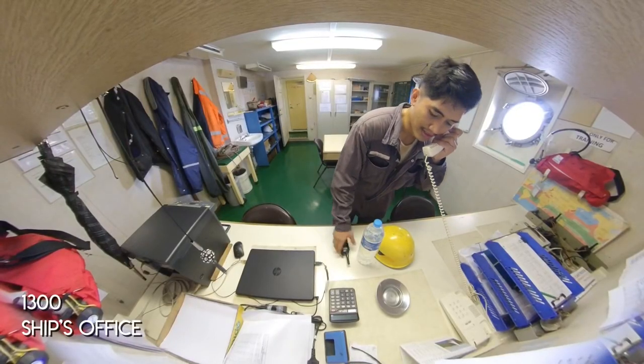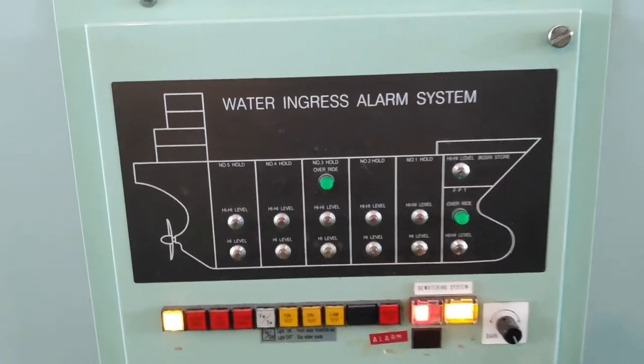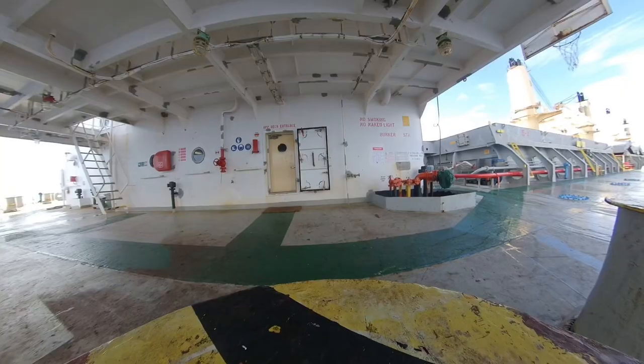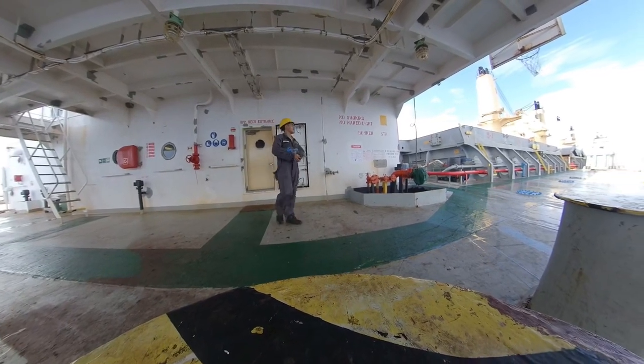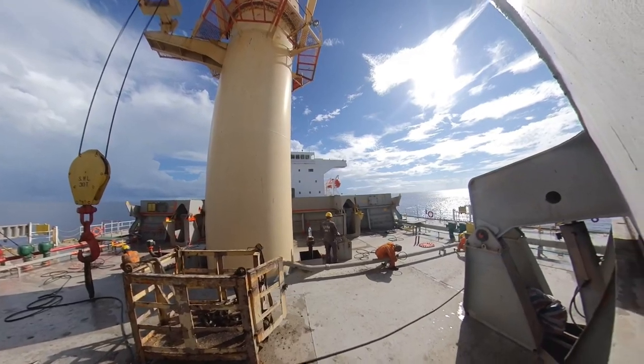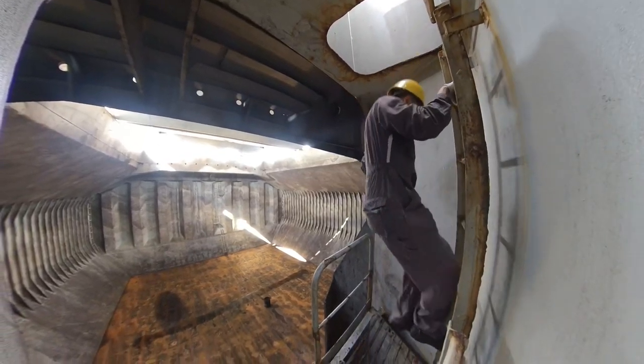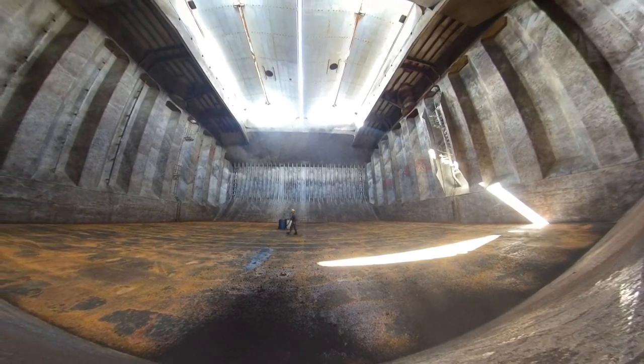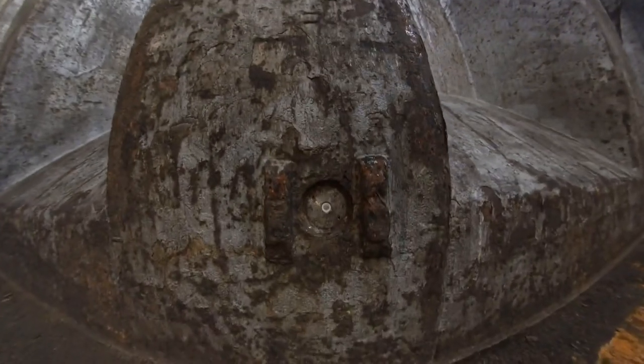In the afternoon, I then proceeded to my last task, which was to check the function of level sensors inside the cargo holds. In this task, I have to be in constant communication with the duty officer on the bridge, since the visual and audible alarm will activate at the bridge. Also in the morning, I asked the bosun to slightly open the hatch covers for the cargo holds to allow air flow. This task is physically demanding since the sensors are located at the bottom of the five cargo holds. These are sensors set to the wall of the cargo hold in order not to be hit during loading. I used a rag soaked with sea water for this test.